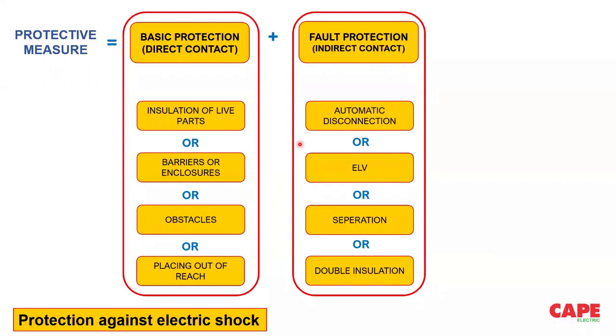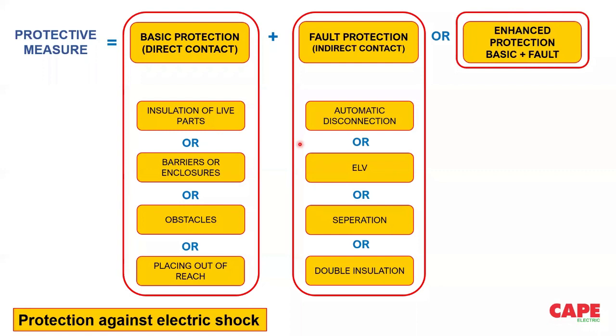If you have an area with computers, then sometimes you may need to go for a separation. If you have a critical place with wet areas, probably you have to go for an extra low voltage situation. So the first job of the verifier, I'm not saying the auditor, verifier, is to understand the safety measures and apply them appropriate to the location. There are measures sometimes where one measure offers both basic and fault protective measure.